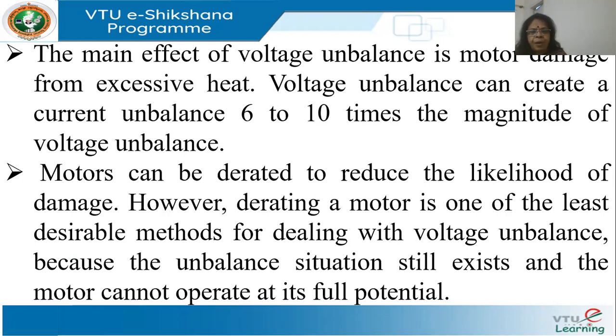Transformers also are derated. For example, supposing you have a 5000 HP motor. What do you understand from that? You understand that you can load up to 5000 HP, right? This is under normal operating conditions when you have only positive sequence currents. So when you have unbalance, you reduce this. Don't operate it at 5000 HP. Operate it at something lesser, maybe 1%, 2% lesser.